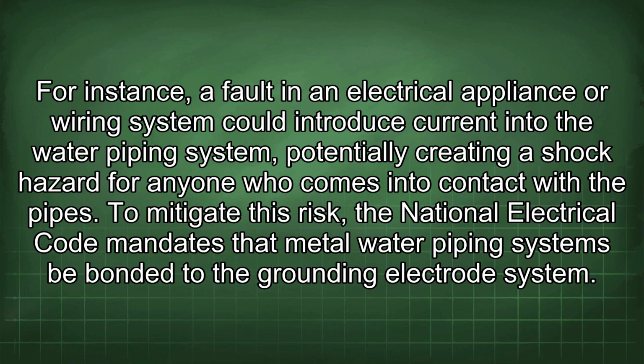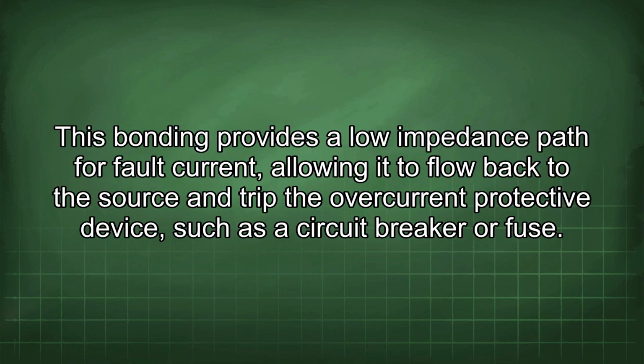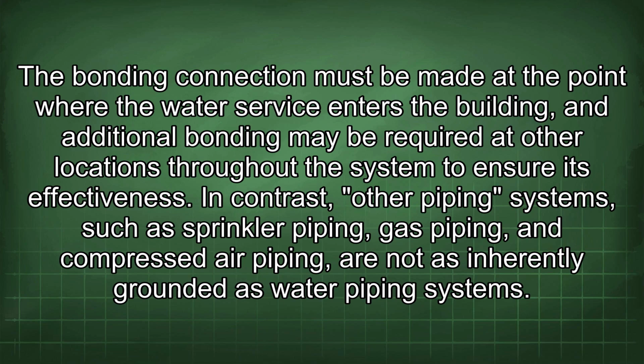To mitigate this risk, the National Electrical Code mandates that metal water piping systems be bonded to the grounding electrode system. This bonding provides a lower impedance path for fault current, allowing it to flow back to the source and trip the overcurrent protective device, such as a circuit breaker or fuse. The bonding connection must be made at the point where the water service enters the building, and additional bonding may be required at other locations throughout the system to ensure its effectiveness.